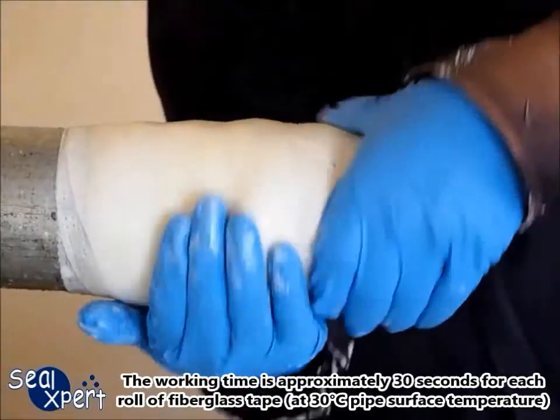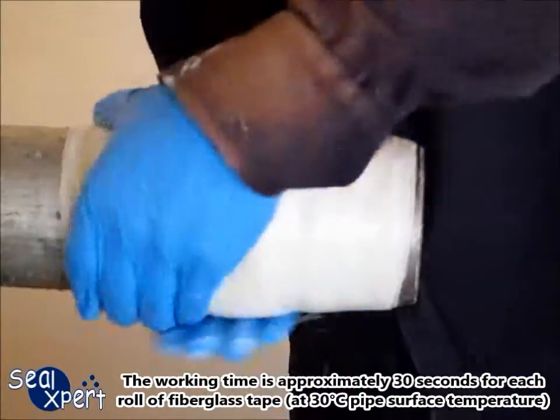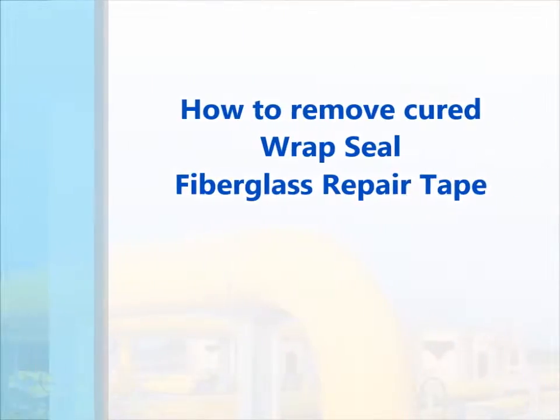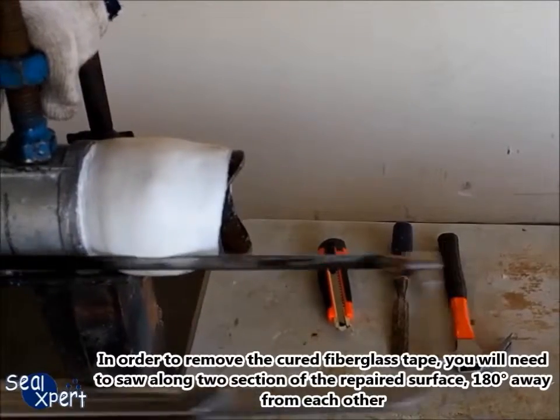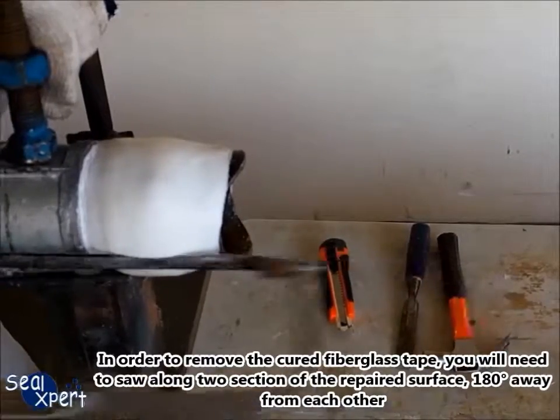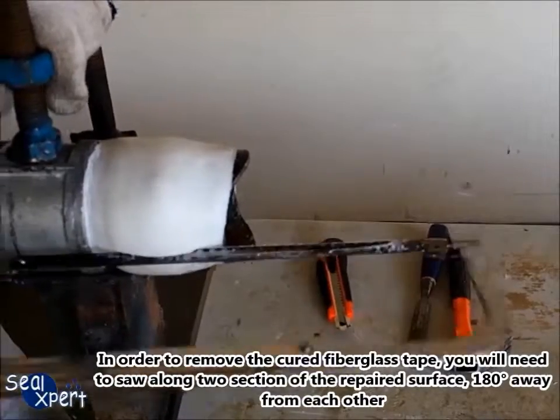The working time is approximately 30 seconds for each roll of fiberglass tape at 30 degrees Celsius pipe surface temperature. After the Wrap Seal fiberglass tape is fully cured, it will attain approximately 80 Shore D hardness. In order to remove the cured fiberglass tape, you will need to saw along two sections of the repaired surface, 180 degrees away from each other.